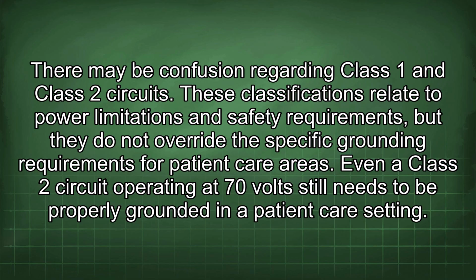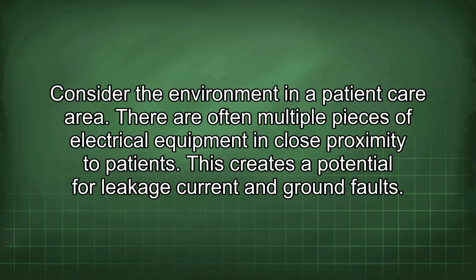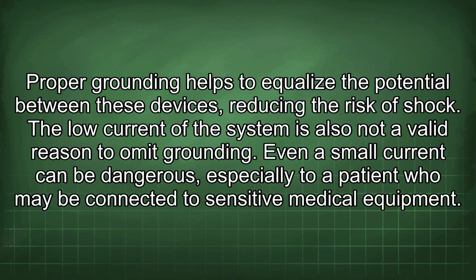There may be confusion regarding Class 1 and Class 2 circuits. These classifications relate to power limitations and safety requirements, but they do not override the specific grounding requirements for patient care areas. Even a Class 2 circuit operating at 70 volts still needs to be properly grounded in a patient care setting. Consider the environment in a patient care area. There are often multiple pieces of electrical equipment in close proximity to patients. This creates a potential for leakage current and ground faults. Proper grounding helps to equalize the potential between these devices, reducing the risk of shock.